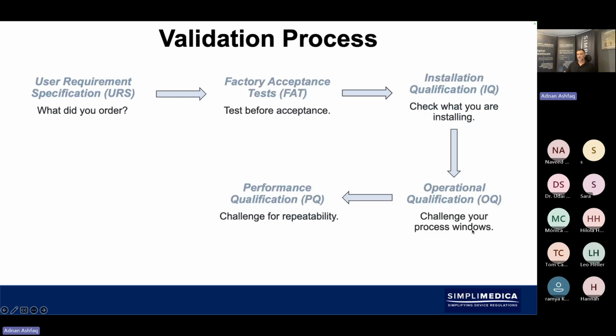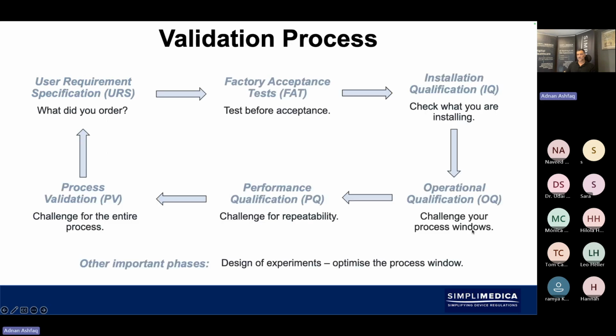So the validation process, when we look at the process as a whole, we should be looking at user requirement specifications, right? So what did we order? That's the user requirement specification. Normally, the user requirement specification would go to the supplier, and that's what they would use to build the equipment. You would then have an opportunity to do factory acceptance testing.